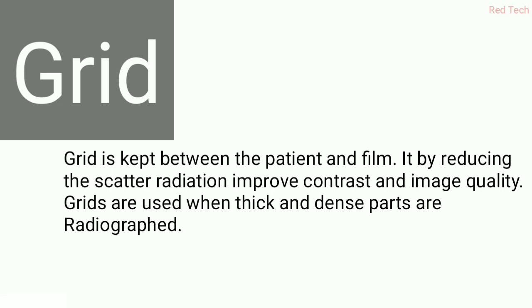Next is the grid. The grid is kept between the patient and the film. It is used to reduce scatter radiation and improve contrast and image quality. Grids are used when thick and dense body parts are radiographed, such as the abdomen, femur bone, or spine. The grid absorbs scatter radiation that comes out during x-ray exposure.